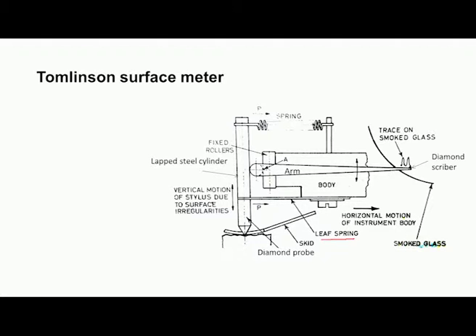Now, during the operation, the body of the Tomlinson surface tester is made to move on the workpiece surface, and because of the asperities present on the workpiece surface, this lapped steel cylinder will move up and down, and this motion is converted into rolling action of the arm with the help of this horizontal cylinder A. So, at the other end of the arm we have this diamond scriber which is in contact with the smoked glass. When the cylinder moves up and down, the diamond scriber makes scratches on the smoked glass.